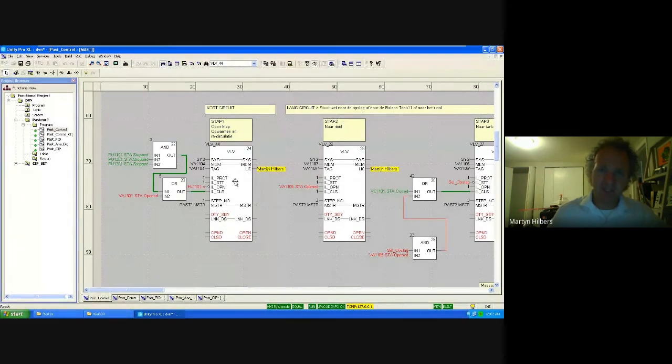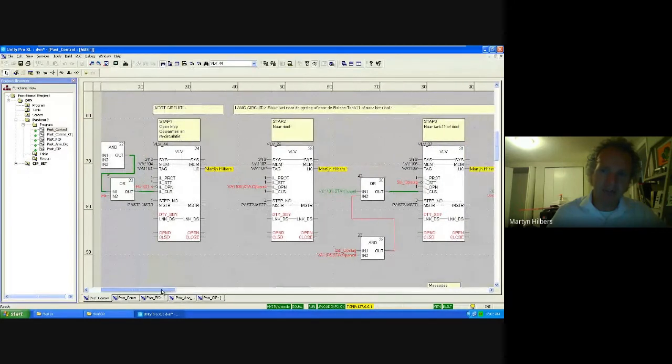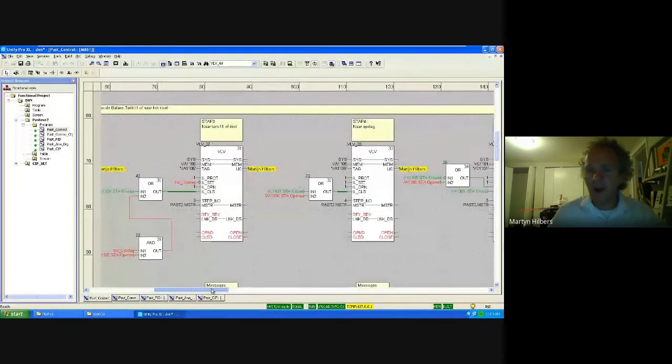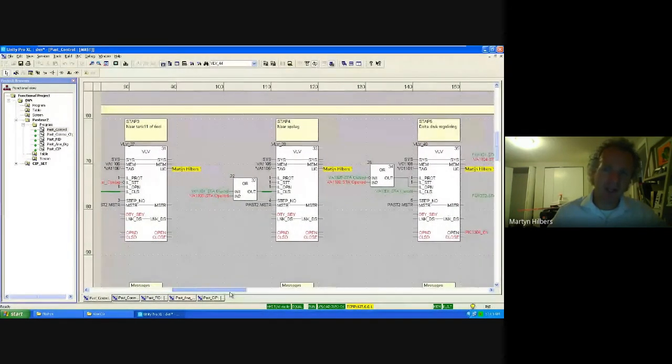And basically those 8 parameters that I was talking about are these. There are 4 interlocks, a step number, a master, and 2 duty standby pins. And every time you use those same 8 parameters to connect. For instance here, I have a close interlock, which is an OR gate: if one of the valves is closed, or I have a route that takes me to my storage, or I've got another valve that's opened, well, then I've got a close interlock. So that's basically your 101 AND and OR gate programming in PLCs.